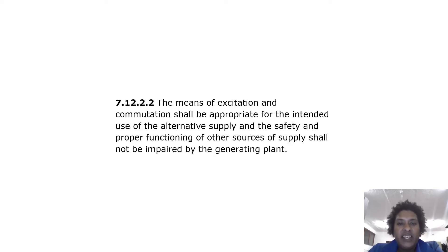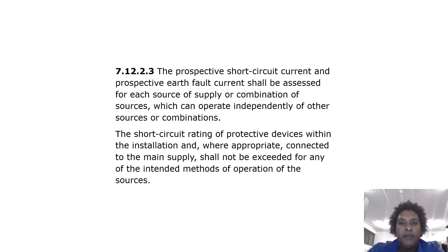All forms of alternative devices such as inverters shall comply with the requirements of 6.16.1. The means of excitation and commutation shall be appropriate for the intended use, and the safety and proper functioning of other sources of supply shall not be impaired by the generating plant. The prospective short circuit current and prospective earth fault current shall be assessed for each source of supply or combination of sources which can operate independently.